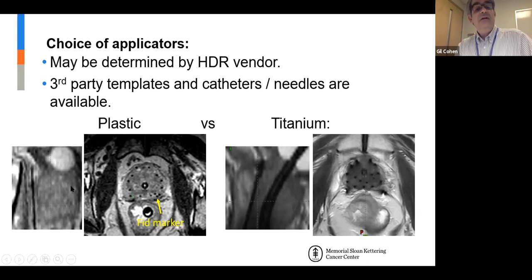With plastic needles, unlike CT, be aware that plastic and air both look black on MRI. So if you have a 4-millimeter tip, you need to be aware of it and subtract it when doing your treatment planning. Finally, when you optimize your treatments, it's not just about visualizing the needles. If you're implanting fiducial markers, for example, because your patient is going to go for external beam or SBRT afterwards, you want to make sure you can visualize those fiducial markers as well.